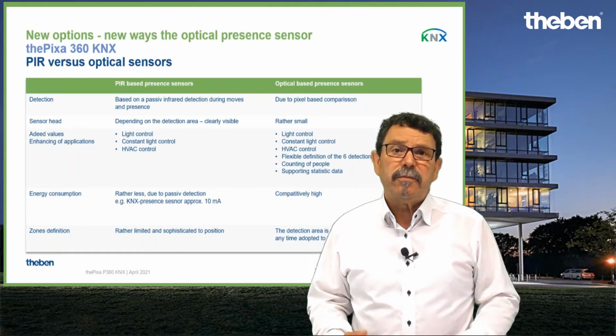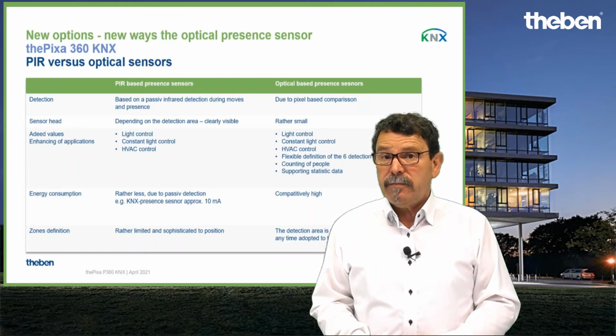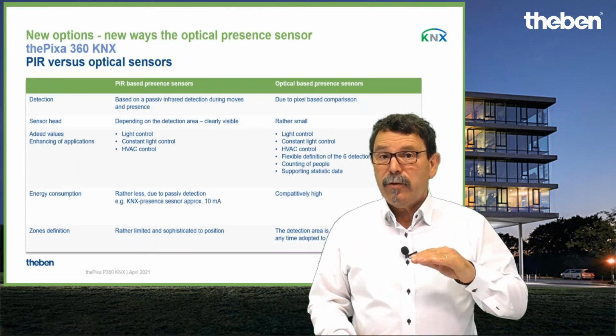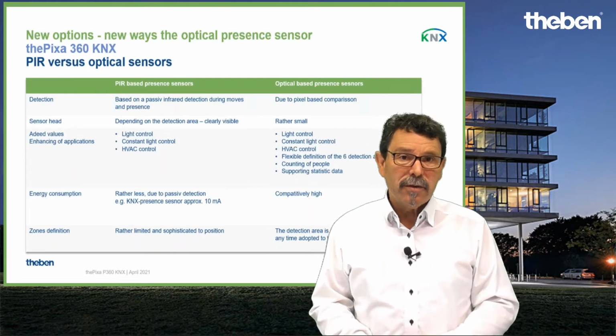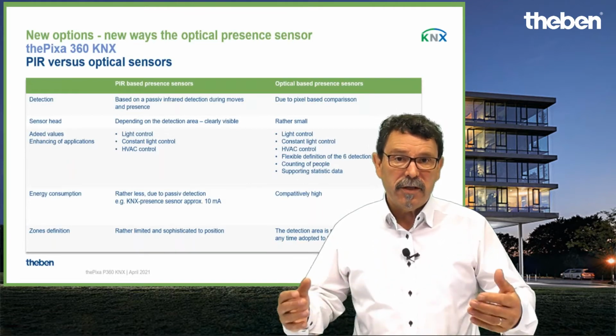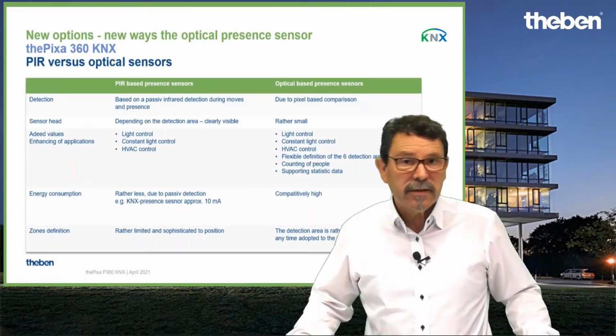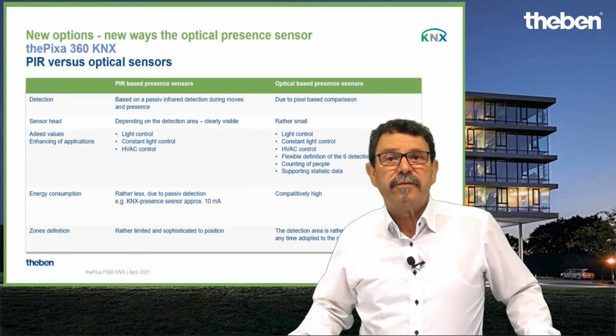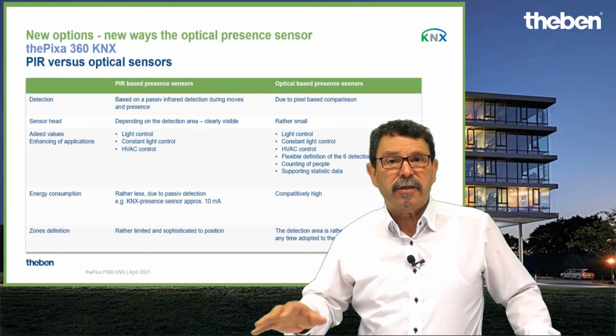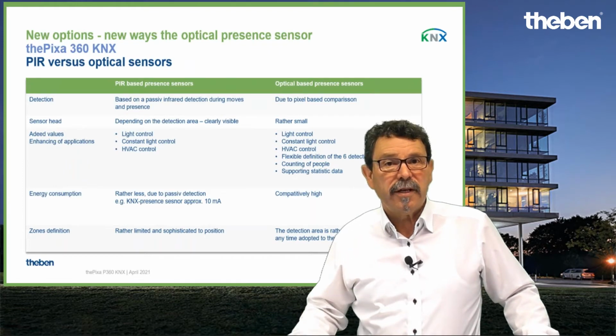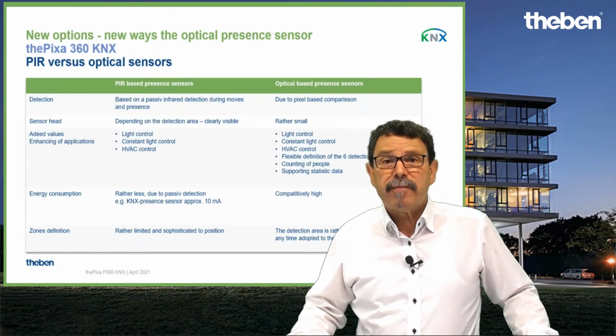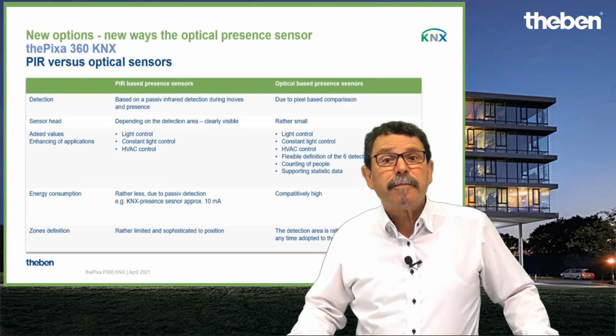We have to confirm, but we know the temperature is sometimes the problem. If you have unstable indoor conditions, meaning the indoor temperature is not climatized, and the gap between ambient temperature and body temperature is not more than 4 K, the PIR sensor definitely is troubled because then the sensitivity is not that good anymore.